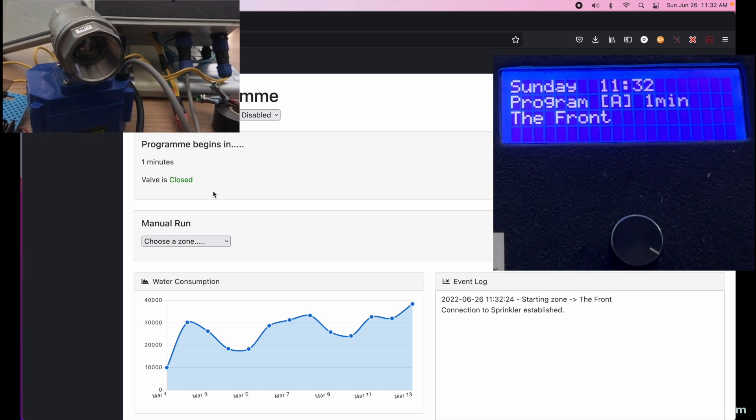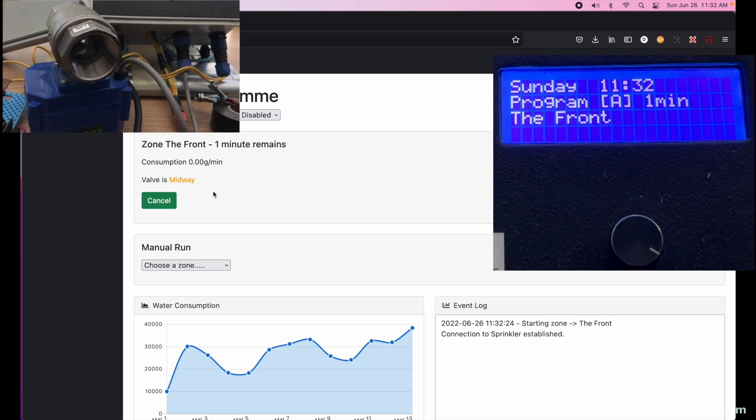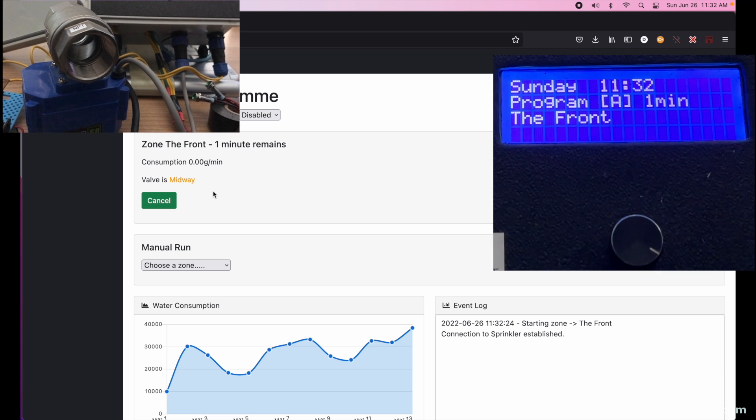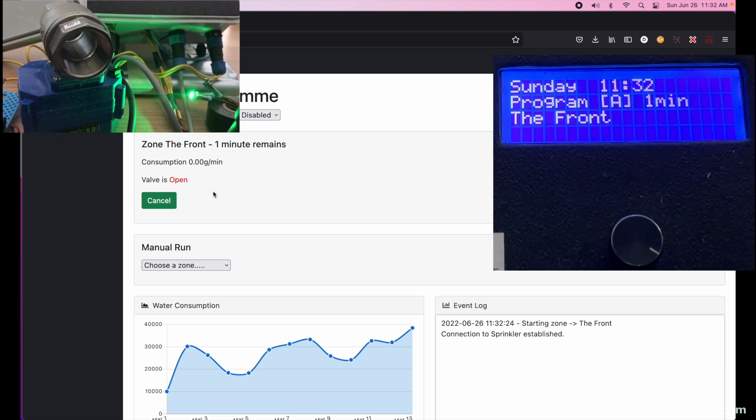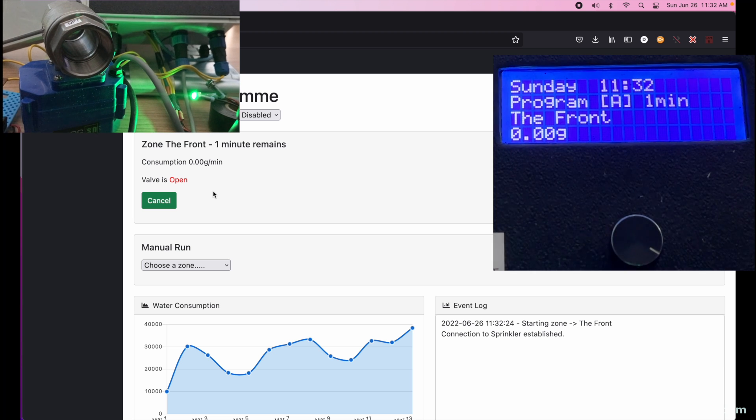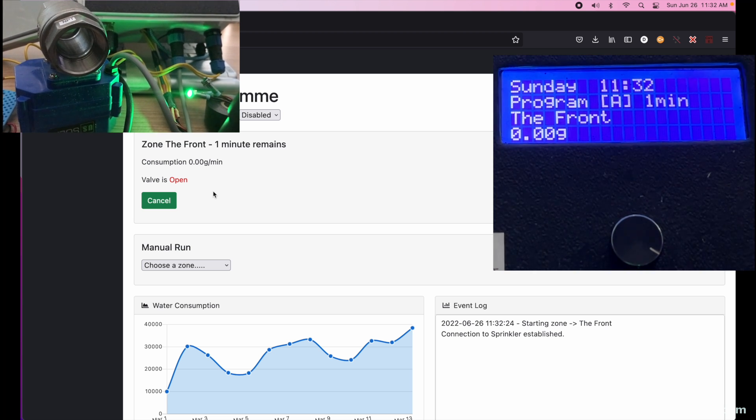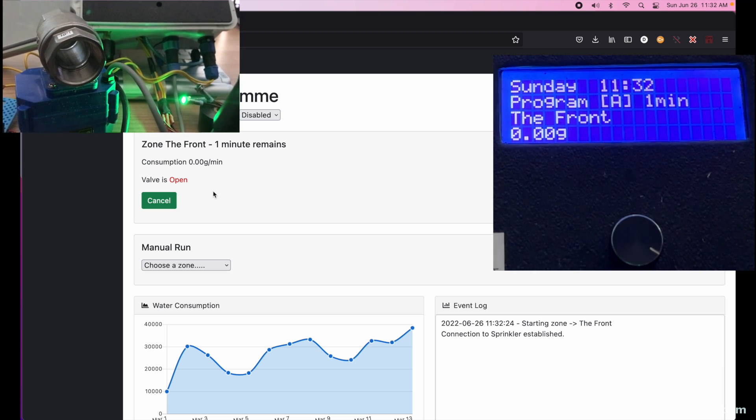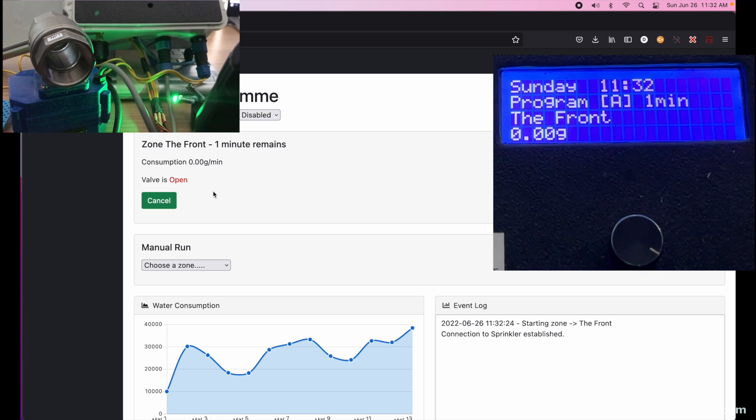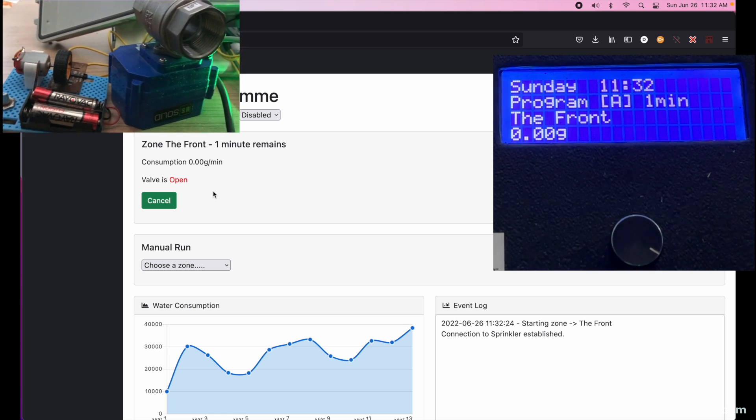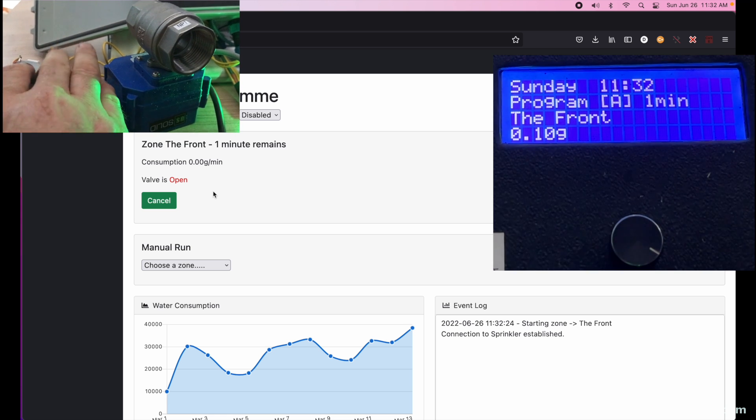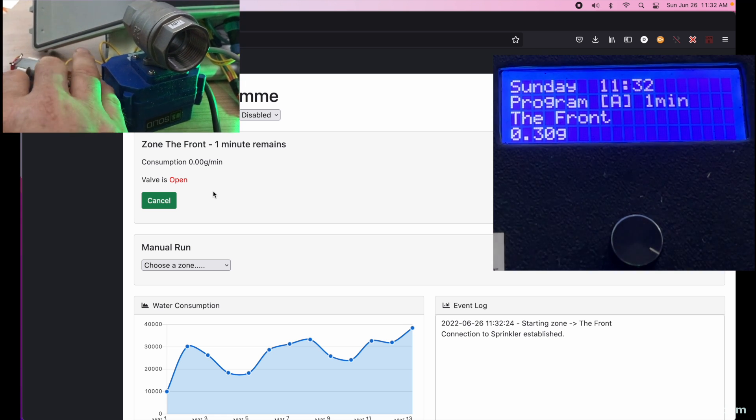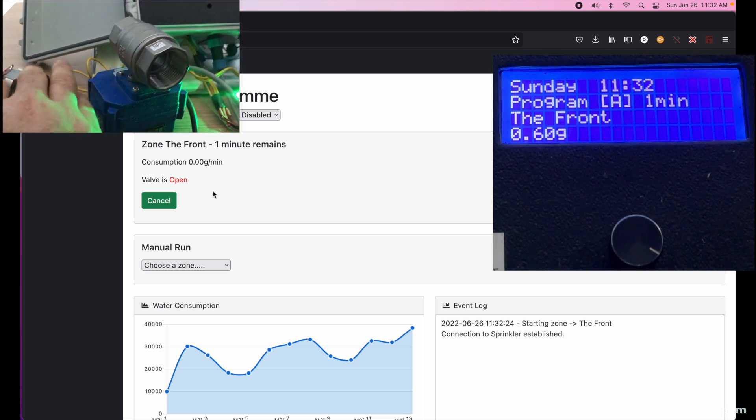We see the event log is updating. Notice the valve status went to orange to midway, and then red to open. The front panel status has changed. The consumption values now appear though it does not work in the web UI, only on the LCD screen, haven't written that yet. I'll test it out now by turning the meter emulator and we could watch it increment on the LCD screen in tenths of a gallon. So that's working just fine.